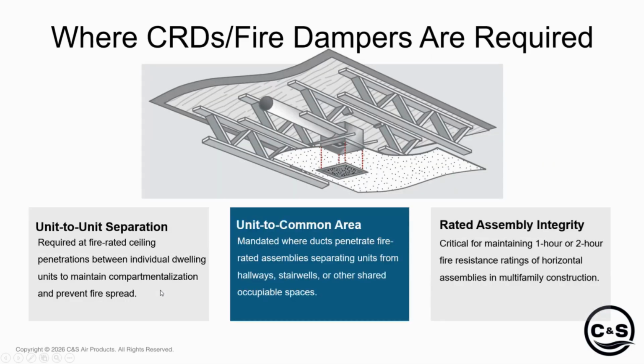Okay. So, understanding what is required for ceiling radiation dampers: anytime you penetrate through the ceiling space, where you're doing a supply or a return, you have to have a ceiling radiation damper behind that opening to protect the space above. And this picture up at the top has a pretty good view of what a ceiling radiation damper installation looks like up into a truss space.